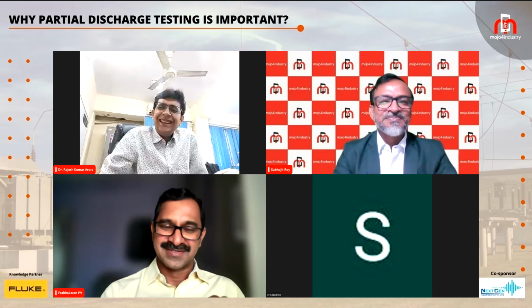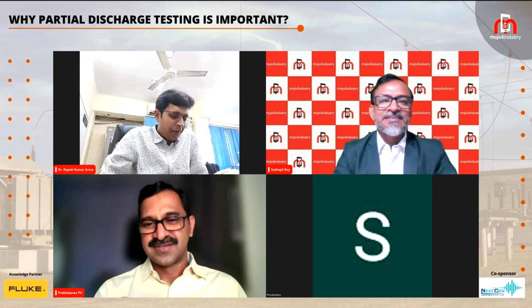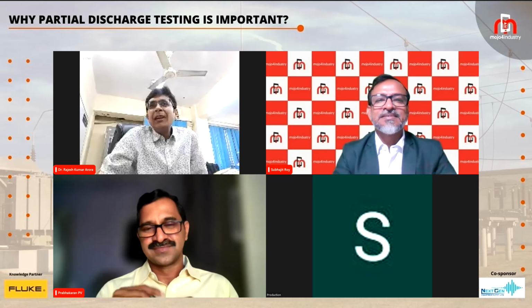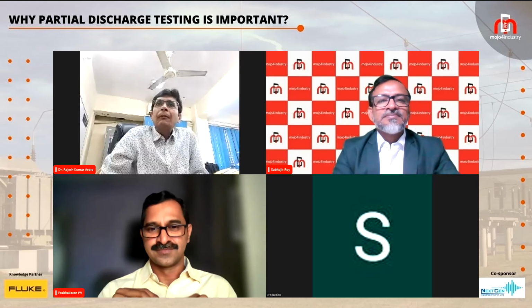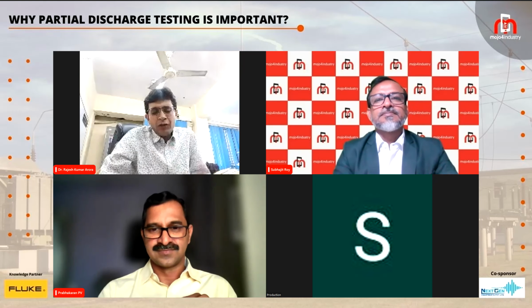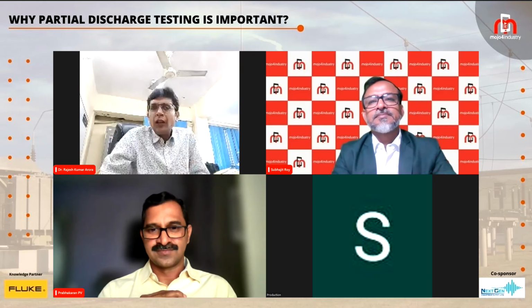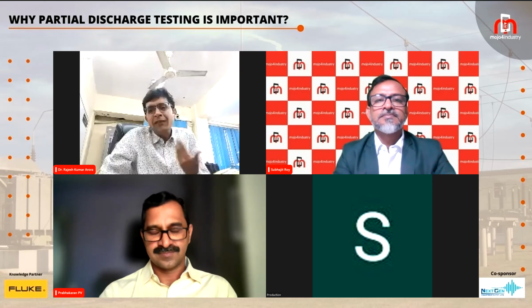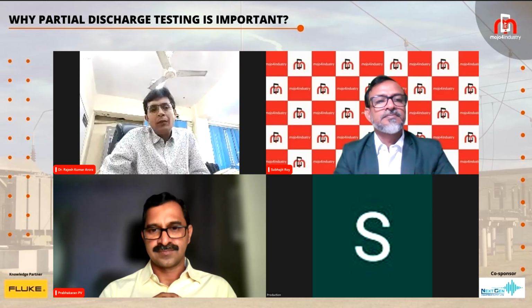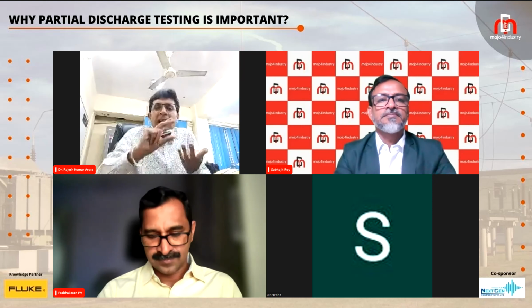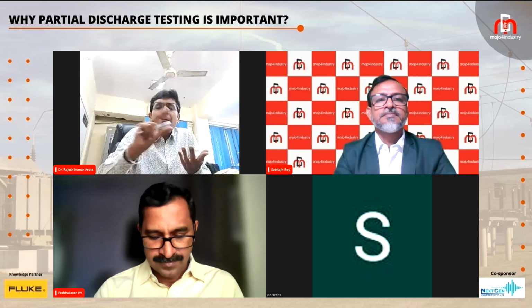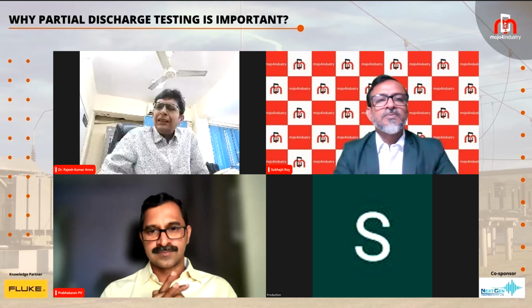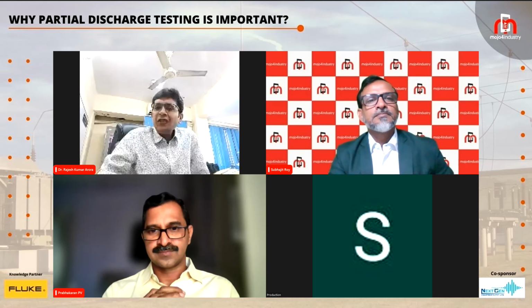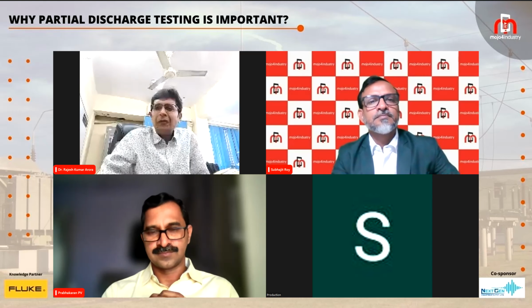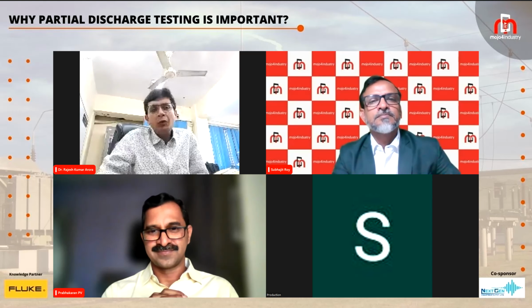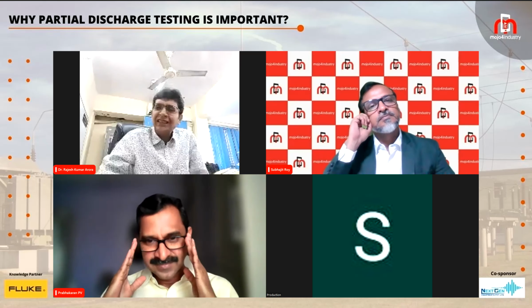Yes, Dr. Arora. Offline versus online depends on the utility and their requirement. Speaking about my own utility, we don't have online monitoring right now—we use portable offline equipment, as and when required, or based on a specific time period given in the maintenance or condition monitoring schedule. That said, online monitoring is always better—it gives you a continuous pattern for all the equipment, there's no doubt about it. If your utility can afford it, nothing is better than that.